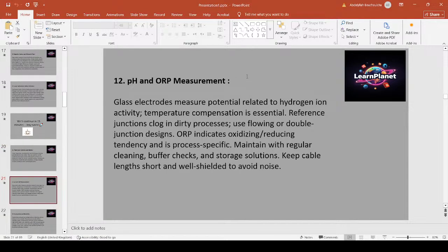12. pH and ORP measurements. Glass electrodes measure potential related to hydrogen ion activity. Temperature compensation is essential. Reference junctions clog in dirty processes. Use flowing or double junction designs. ORP detects oxidizing or reducing tendency, and is process specific. Maintain with regular cleaning, buffer checks, and storage solutions. Keep cable length short and well shielded to avoid noise.